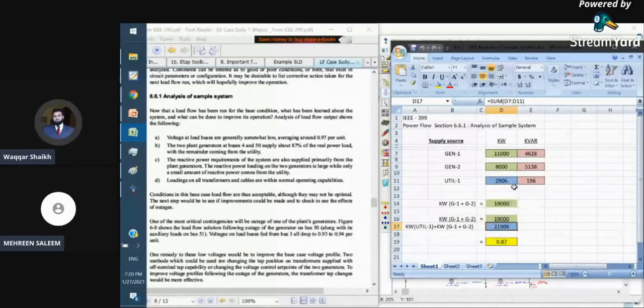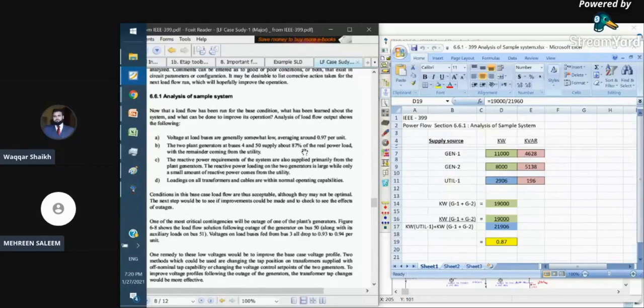Okay, and if we divide the two generators' active power by the overall active power flowing into the network, we find that it's 87%, if you do this calculation by taking the result from ETAP and verifying it. Okay, so you can see here that it's matching with what it's saying. So it means it's showing exactly the same results which are shown in the example.